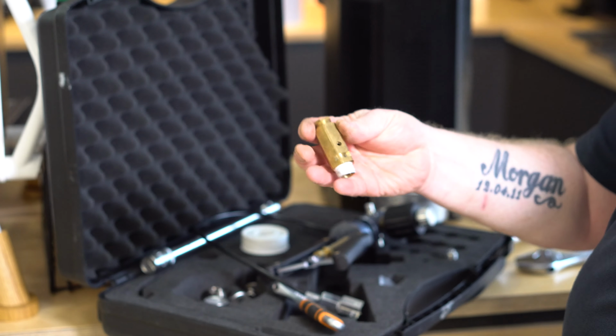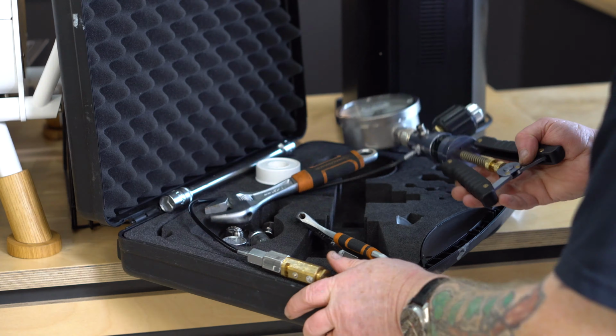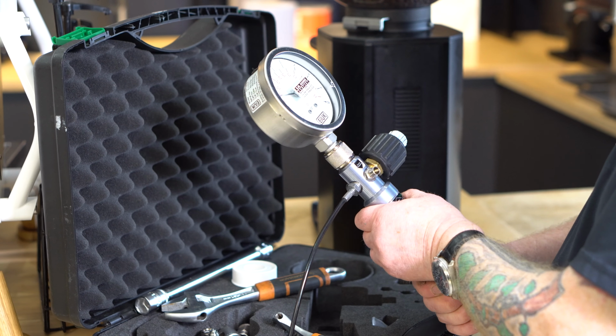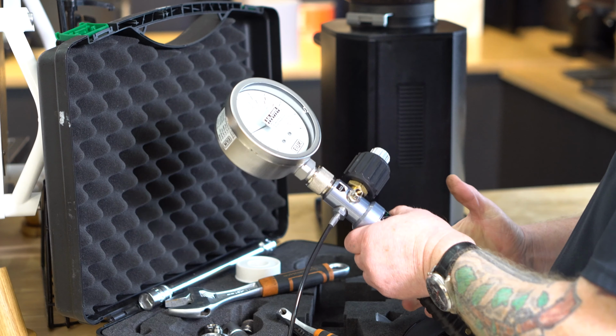Then we are removing the safety valve, and then we're replacing it with a new safety valve. We use a calibrated hand pump to make sure the safety valve releases at the correct pressure. We're looking for the fail-safes on the machine, making sure the anti-vac is releasing correctly, and then we're looking at the pressure switch, which tells the machine to stop building pressure at a certain temperature. If it's not, we can replace this on site or we can adjust accordingly.